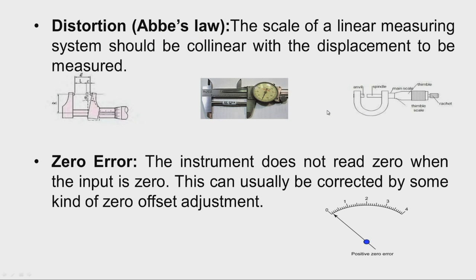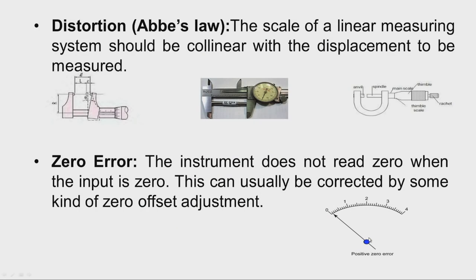Another term is zero error. The instrument does not read zero when the input is zero. This happens due to change in dimensions of internal components caused by variation in temperature. It can be adjusted using a zero offset adjustment provided on the instrument. When there is no signal applied and the pointer shows some deflection, this is known as zero error or zero drift.